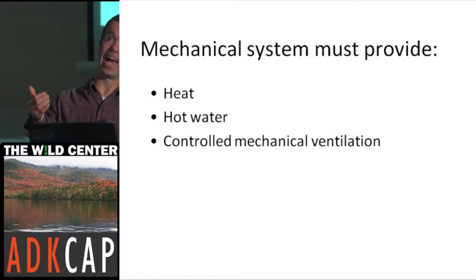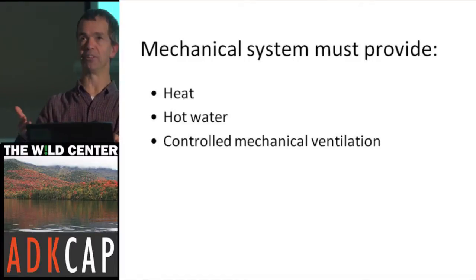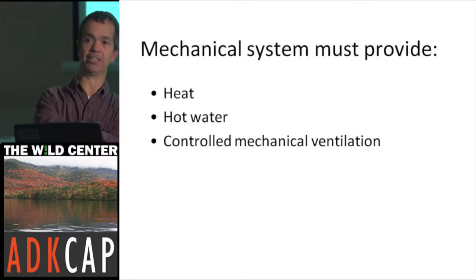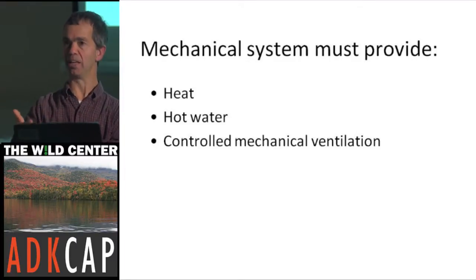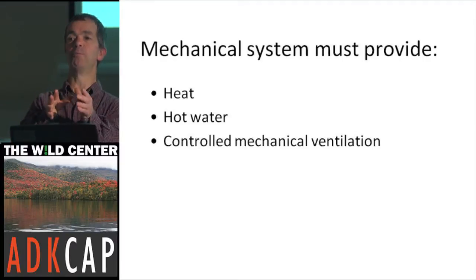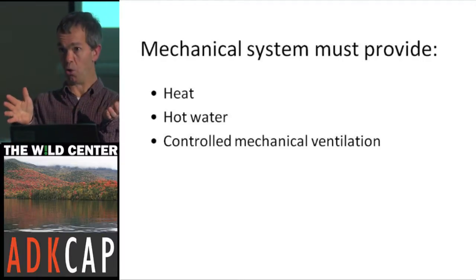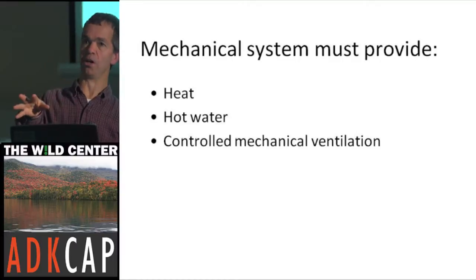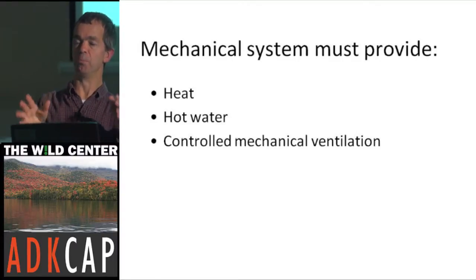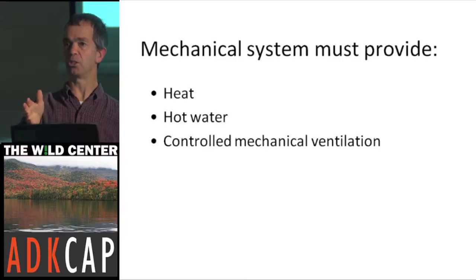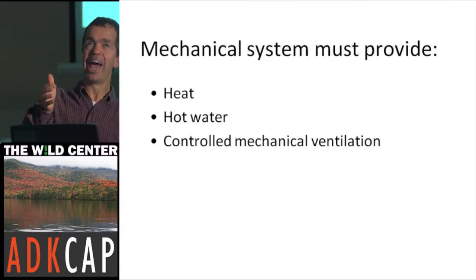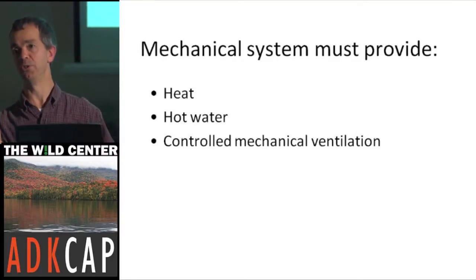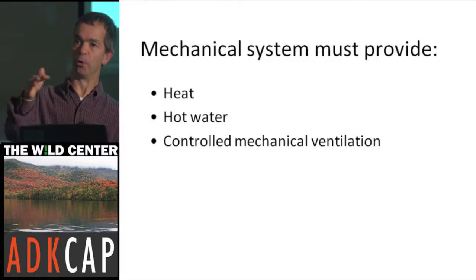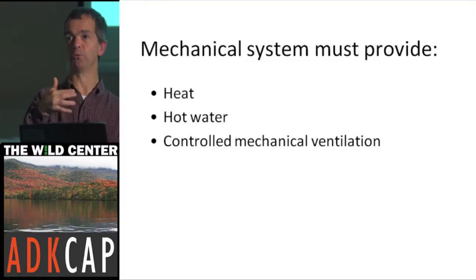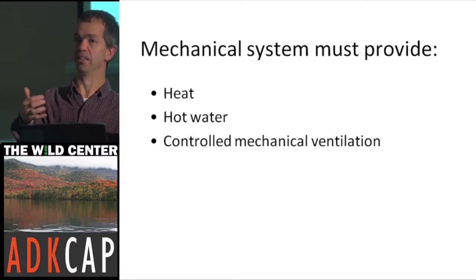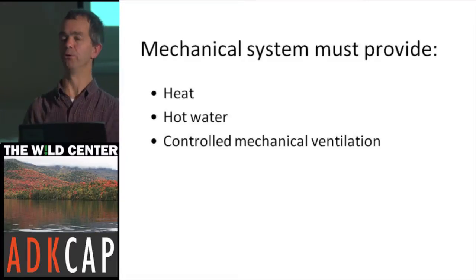To avoid the additional expense of converting everything to hydronic, and since we needed the ductwork for mechanical ventilation, we came up with what we call a fan coil. A fan coil is similar to a furnace but much, much reduced. It asks for about 45,000 BTUs per hour, as opposed to the furnace, which was 250,000 BTU, like 6 big burners in there.